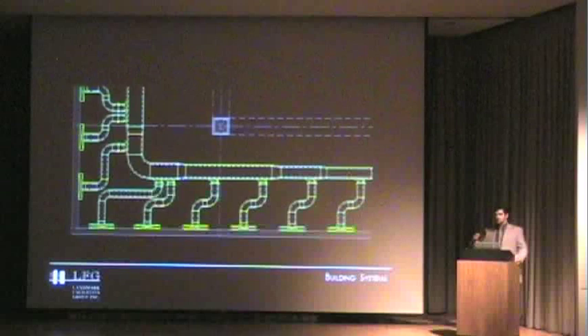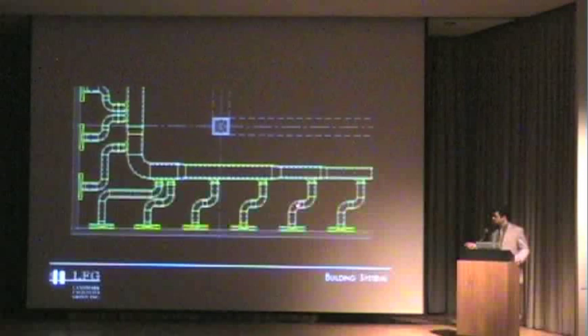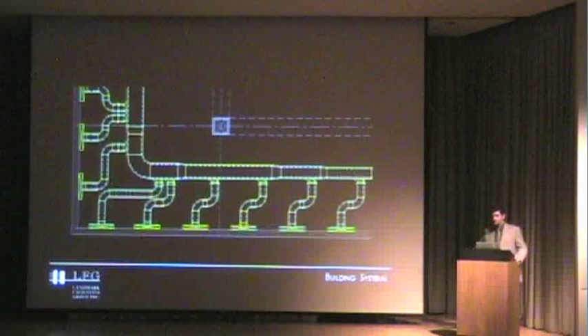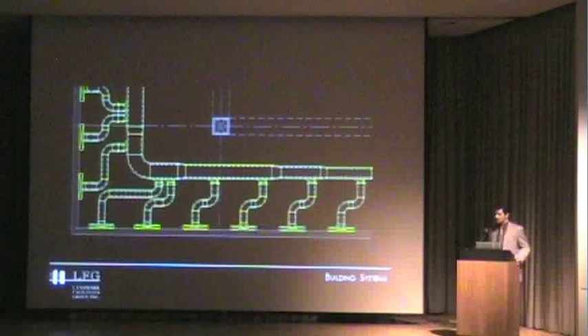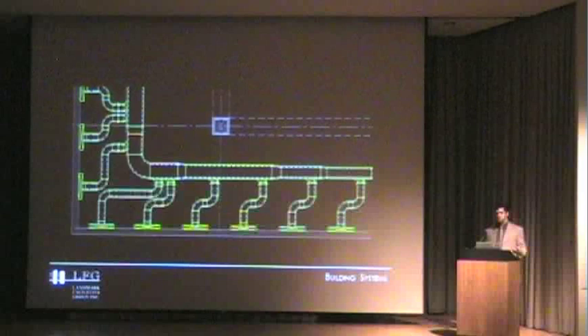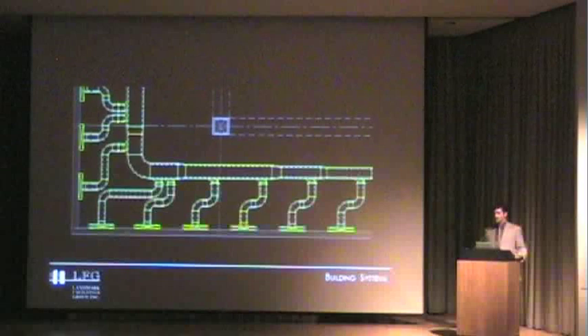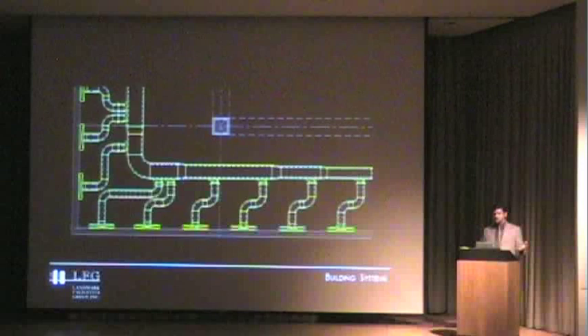That air noise gets absorbed by two elbows, which were designed in, and we did go back and forth a number of times with the contractors, who eventually relented, but they're questioning why they couldn't just do a straight run into the duct here. But what we're aiming for is a user experience, a visitor who can go in and enjoy the architecture of this building without having to combat air noise or see where these systems are. We don't want them to impede on the user experience at all.